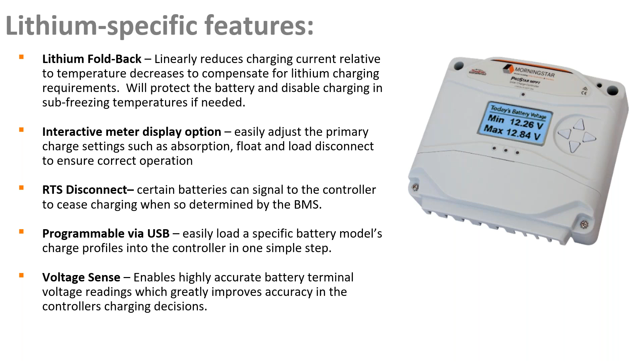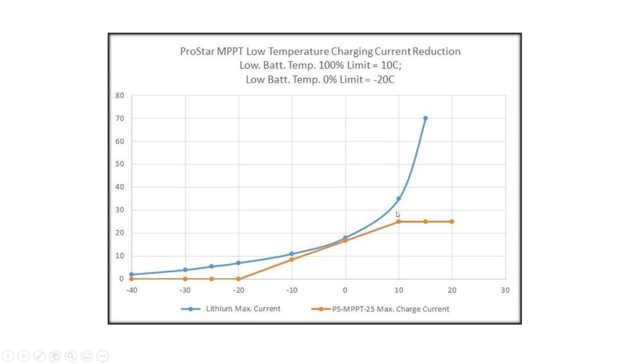This graph just illustrates the lithium foldback feature I was talking about. You can again see here, I should have pulled it up as I was talking about it, you can have this linear derate approximating the curve. This curve is provided by the battery manufacturer that says, okay, as temperatures get colder, we can accept this much current, we can accept this much current here and that much current there, and then you've got to cut it off completely. So we can approximate that curve with a linear derate with that low temperature foldback. And then there are also some advanced settings, as I mentioned, that you'll find in MSView. Some of them are available on the meter display as well, on the controllers that have those equipped.